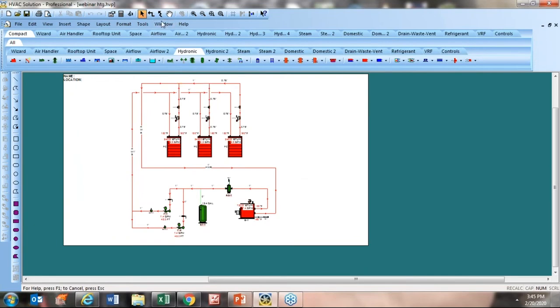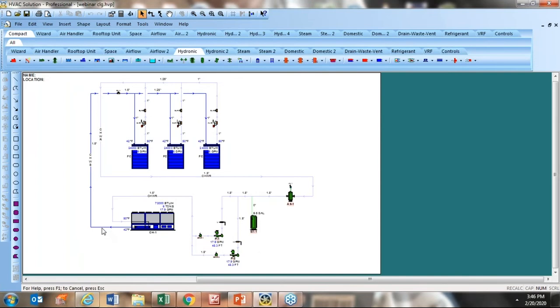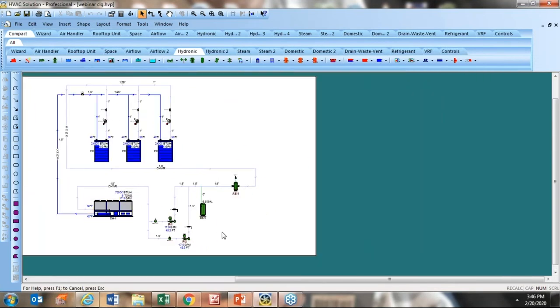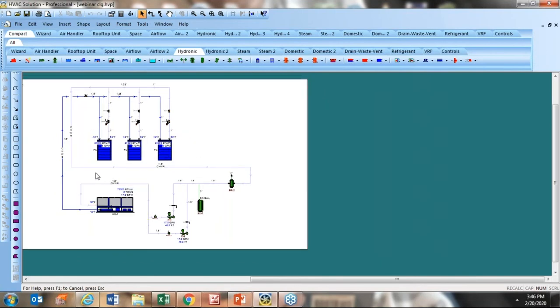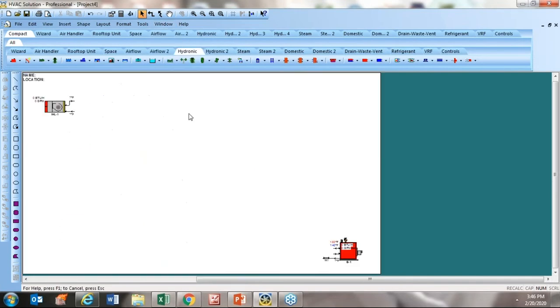You can also use it for a cooling job — the pipe color is temperature-dependent. In order for it to do its calculations, you need to put in two pieces of information: loads in BTUs per hour and pipe lengths. If you live with all the other default values, the software will produce all of the technical output very quickly. Let me get back to the one I was working on.